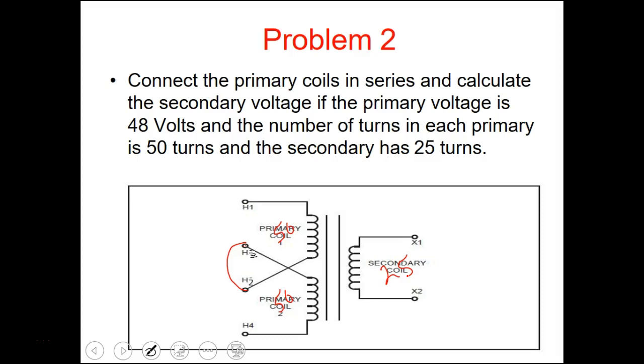So when they're parallel, you're lowering the voltage, which means the current has to go up in the primary to create that power. So the windings are only designed around a certain current, right? You understand? So in parallel, each one of them would get, like I said, if each one of them needed 2 amps, then that would be split. If the primary needed 2 amps, it would split between the two, right? Here, if we put them in series, then we require less current to do what? To provide that power, right? So now if they're rated at 1 amp, this would be 1 amp and this would be 1 amp.